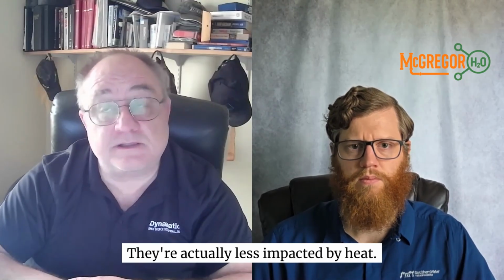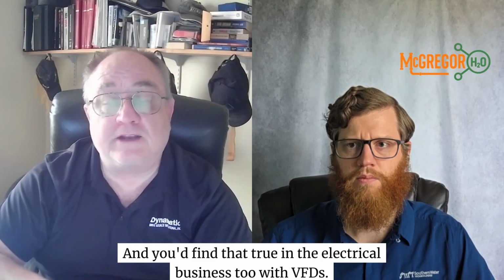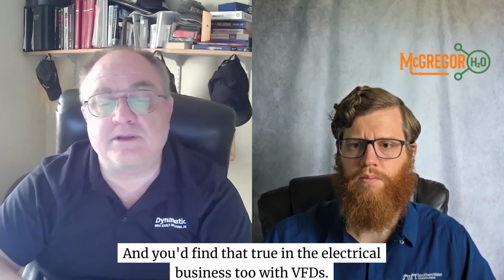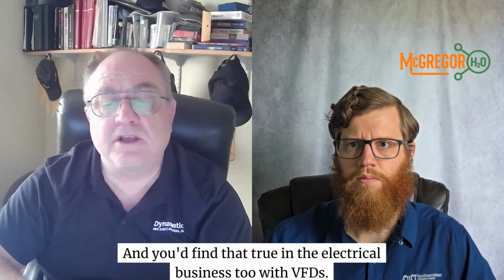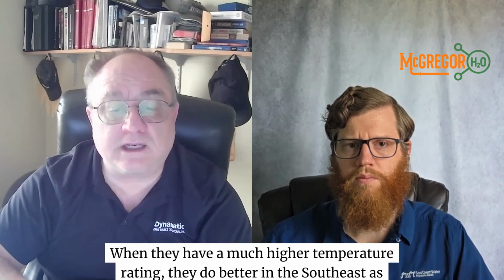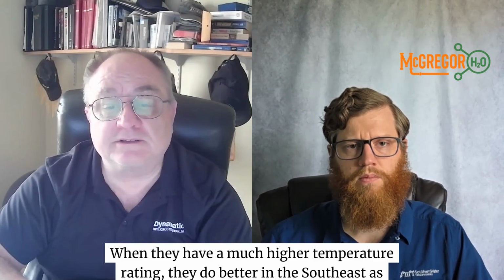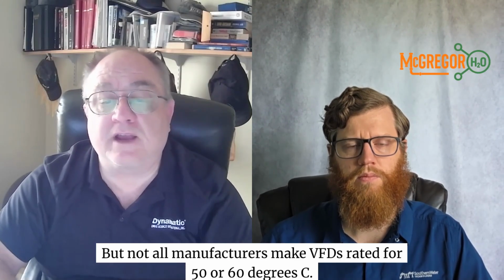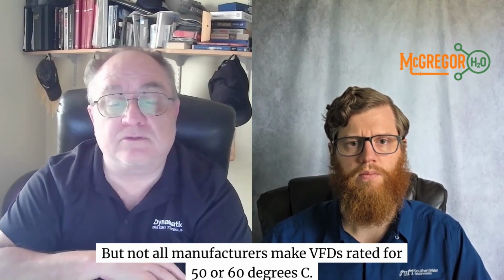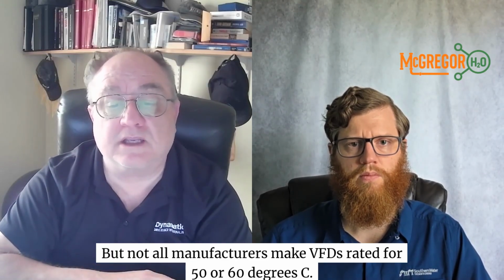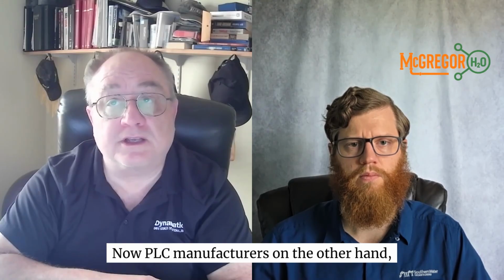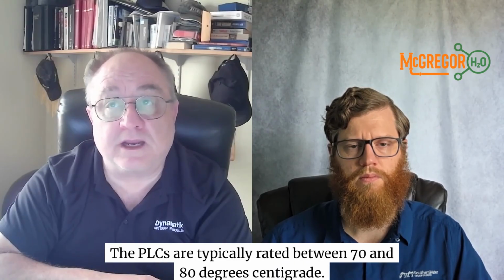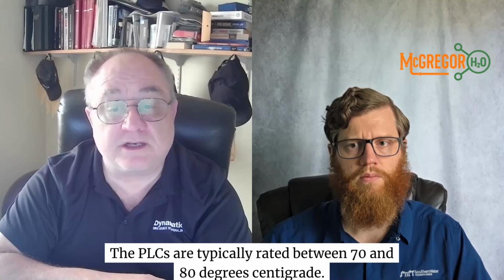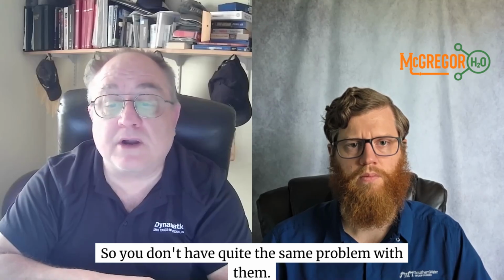They're actually less impacted by heat. And you'd find that true in the electrical business too with VFDs. When they have a much higher temperature rating, they do better in the southeast as well. But not all manufacturers make VFDs rated for 50 or 60 degrees C. Now, PLC manufacturers, on the other hand, the PLCs are typically rated between 70 and 80 degrees centigrade. So you don't have quite the same problem with them.